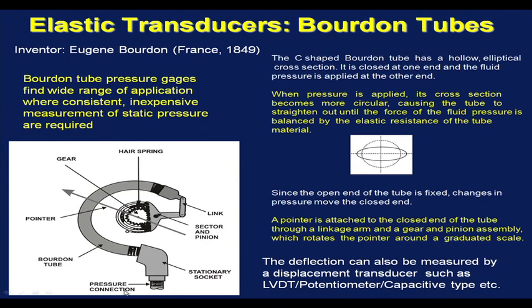The fluid whose pressure I am going to measure is applied here, and this end is rigidly fixed. A pointer is connected to the sealed end of the tube through a gear and linkage system.